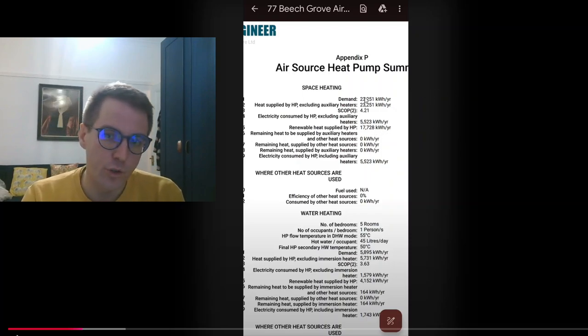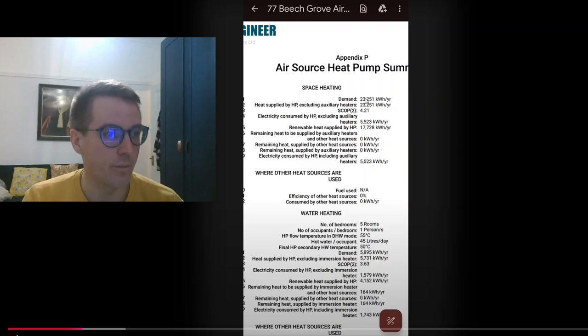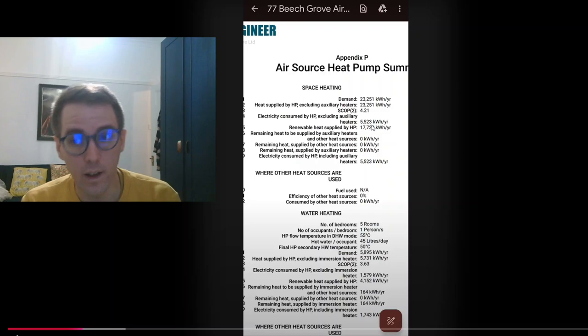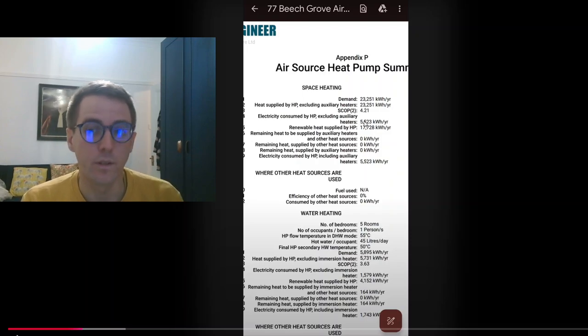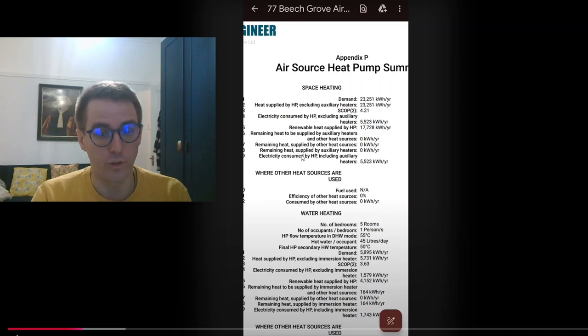So to produce the 23.25 megawatt hours of heat that we demand, it will use 5.5 megawatt hours of electricity. And so I go through how much that might cost. So why don't we do a little pause and I'll get the maths up.